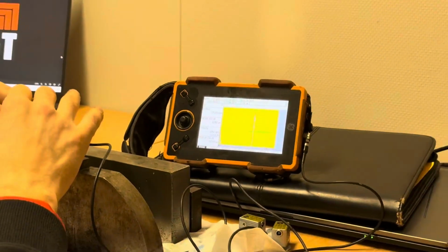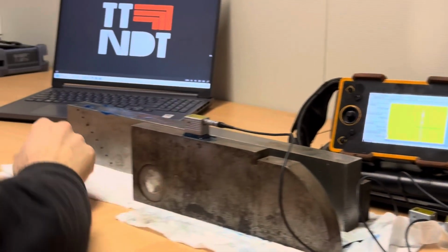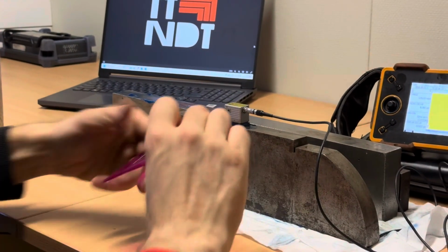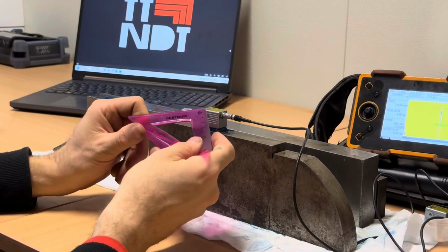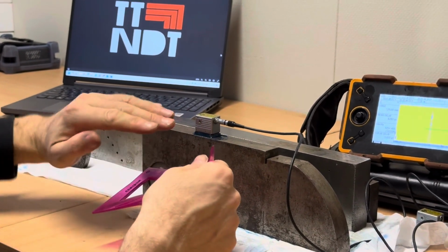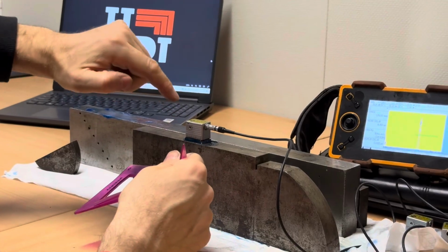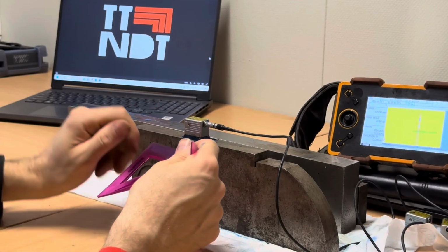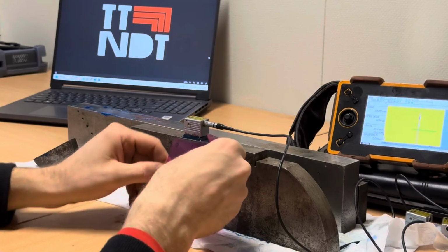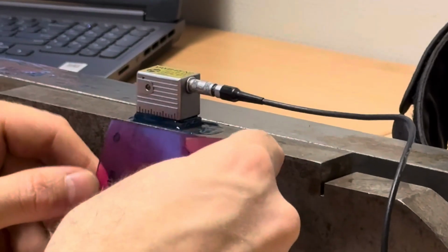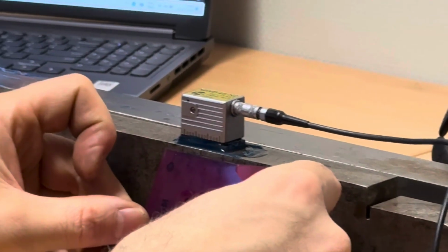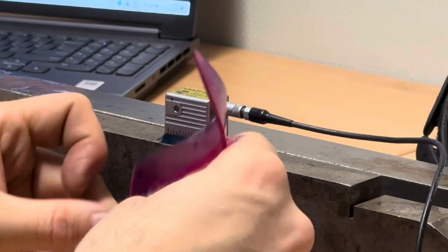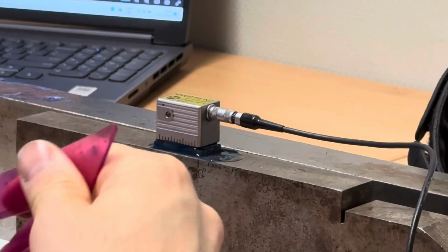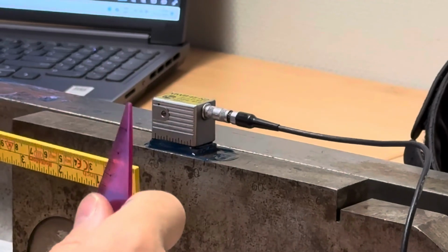So now let's take a careful look. Let's check the angle. The sample itself might not be exactly 45 degrees. If it was worn down unevenly, for instance, it could be 46 or 47 or 43 or 43 and a half, and so on. Our x-axis measurement was 12 millimeters, so we will measure 12 millimeters from the designated start point, and then we will check.